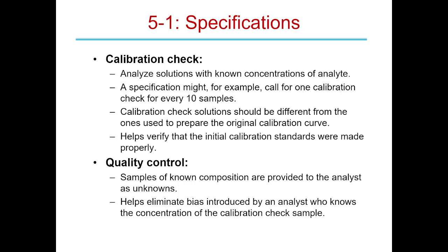Yeah, it's not every 10, it's every 100. Because there's a lot of pressure to get samples turned around, right? And this obviously slows you down. But it's incredibly vital, actually. It keeps the lab from drifting off and giving bad results. Yeah. This is one of the most important things you can do to keep systematic errors out of your system.